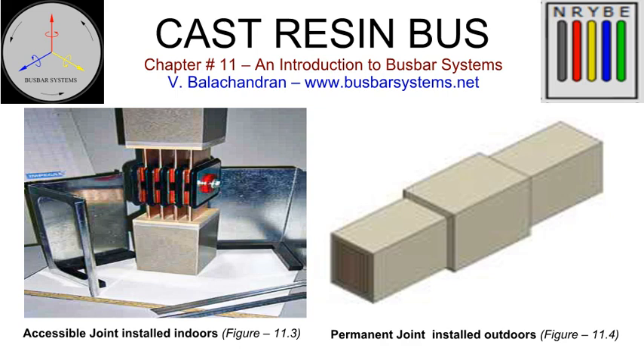Several manufacturers have both busways and cast resin buses in their product range. They can offer a hybrid combination of cast resin bus and busways for a cost-effective solution. Cast resin buses, with a degree of protection of IP68, are installed outdoor, while busways with a degree of protection of IP55 are installed indoors. Special site joint assembly connects them indoors.